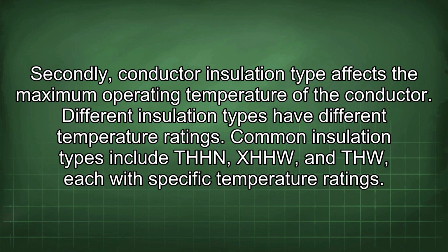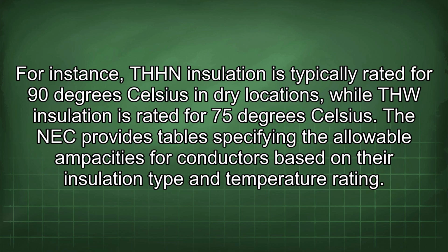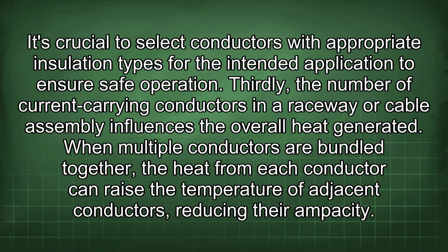Secondly, conductor insulation type affects the maximum operating temperature of the conductor. Different insulation types have different temperature ratings. Common insulation types include THHN, XHHW, and THW, each with specific temperature ratings. For instance, THHN insulation is typically rated for 90 degrees Celsius in dry locations, while THW insulation is rated for 75 degrees Celsius. The NEC provides tables specifying the allowable ampacities for conductors based on their insulation type and temperature rating. It's crucial to select conductors with appropriate insulation types for the intended application to ensure safe operation.